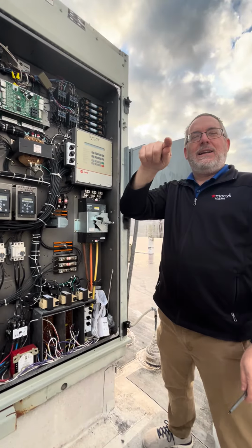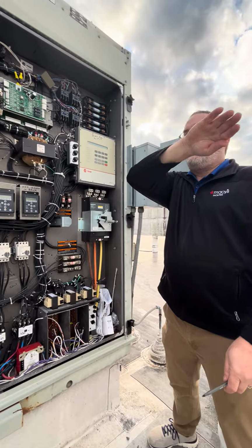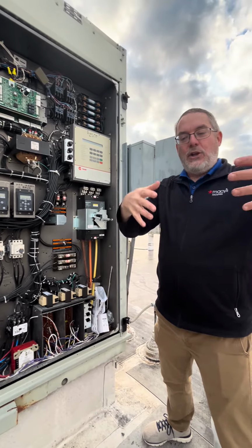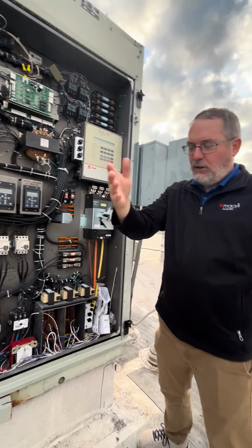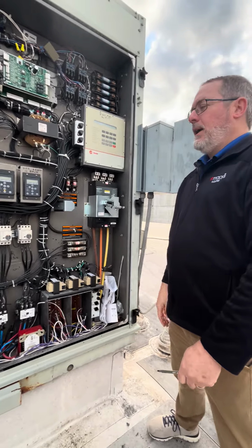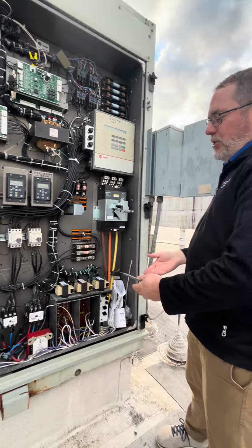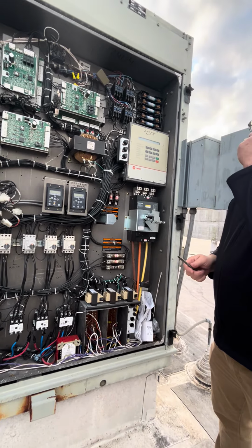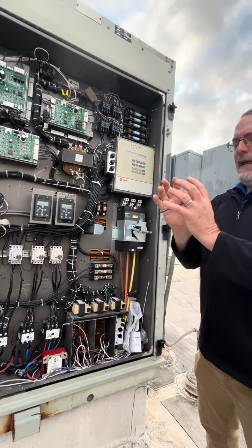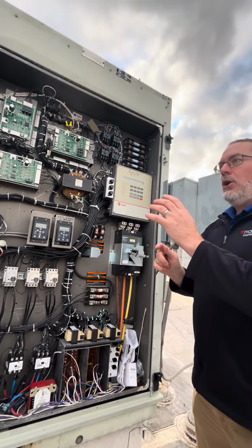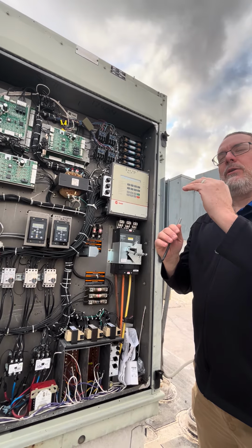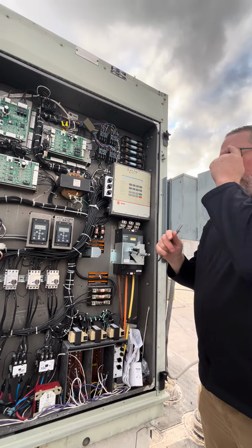The humidity looks like this instead of where you have mechanical running at some level all day when you had a lot of heat, like BTUs, like a chiller. So some of the strategy changes we've made to rooftops like this is we'll do some offsets in the program, meaning, okay, we're getting up towards 74 degrees, we're getting close to set point.